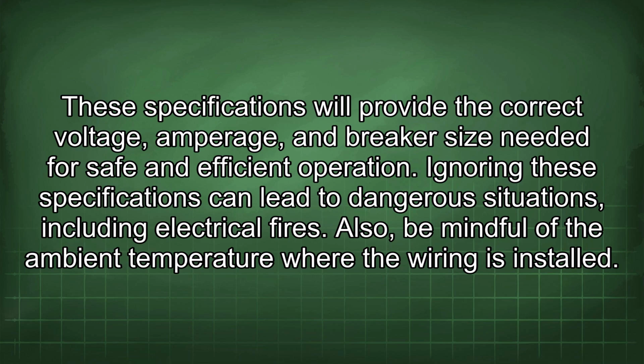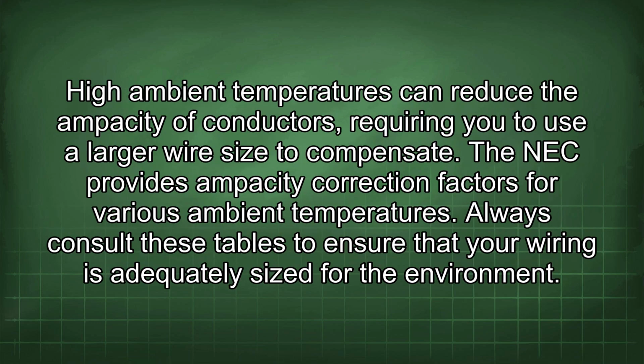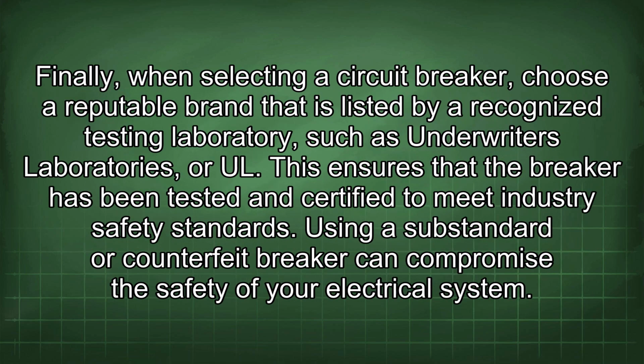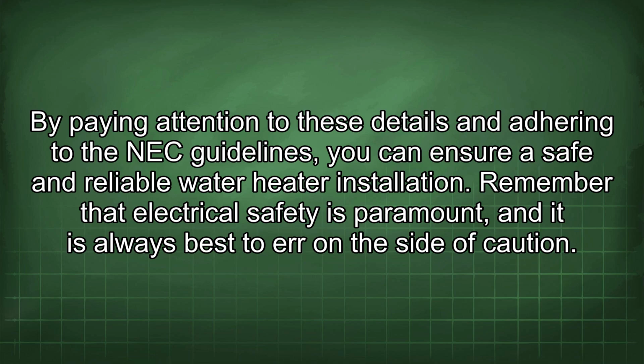Also, be mindful of the ambient temperature where the wiring is installed. High ambient temperatures can reduce the ampacity of conductors, requiring you to use a larger wire size to compensate. The NEC provides ampacity correction factors for various ambient temperatures. Always consult these tables to ensure that your wiring is adequately sized for the environment. Finally, when selecting a circuit breaker, choose a reputable brand that is listed by a recognized testing laboratory such as Underwriters Laboratories, or UL. This ensures that the breaker has been tested and certified to meet industry safety standards. Using a substandard or counterfeit breaker can compromise the safety of your electrical system. By paying attention to these details and adhering to the NEC guidelines, you can ensure a safe and reliable water heater installation. Remember that electrical safety is paramount, and it is always best to err on the side of caution.